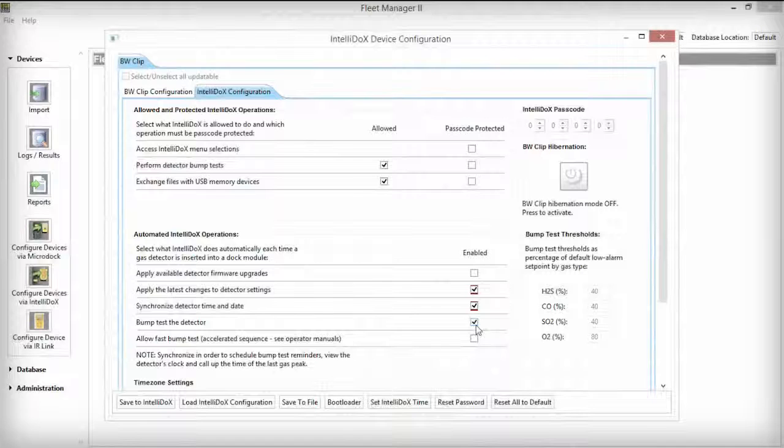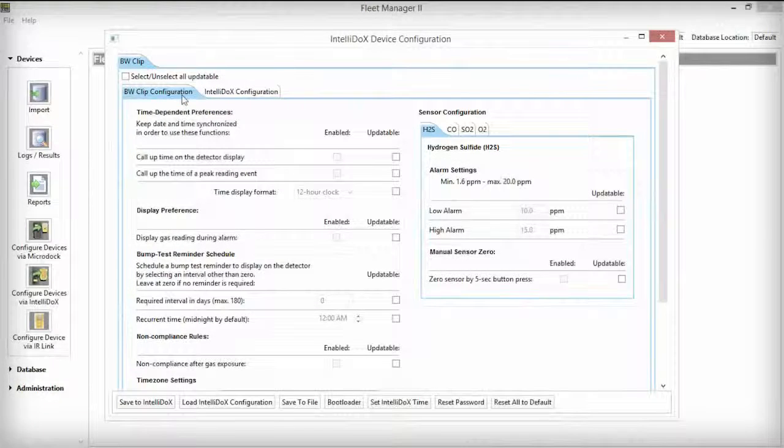Leave Bump Test the Detector selected if you want the IntelliDox to automatically bump test a detector as it is inserted into an IntelliDox. Now, you are set to modify detector configurations by selecting the BW clip configuration tab. Next to the Non-Compliance After Gas Exposure setting, select Updateable first, then Enabled.